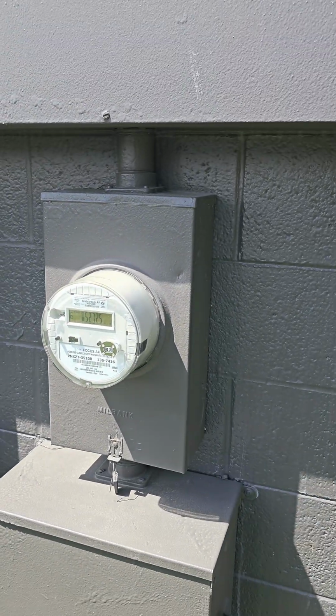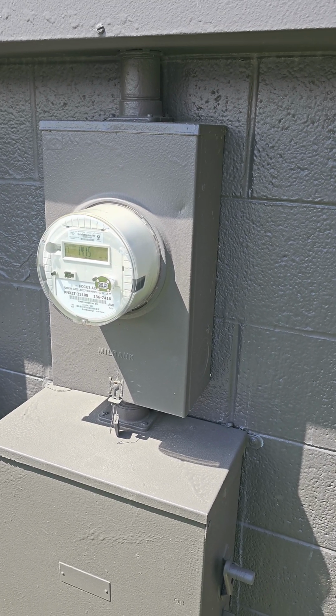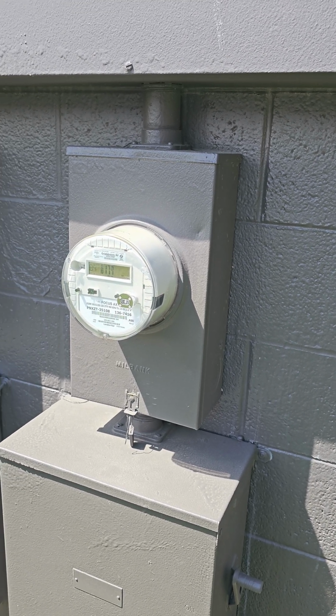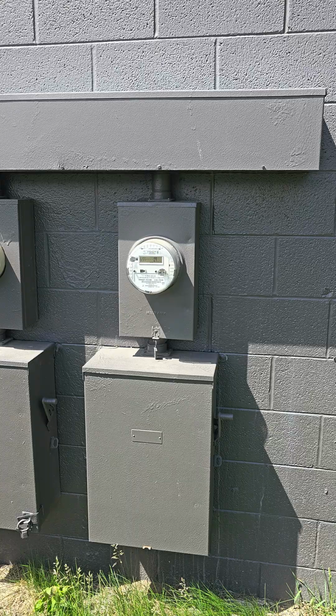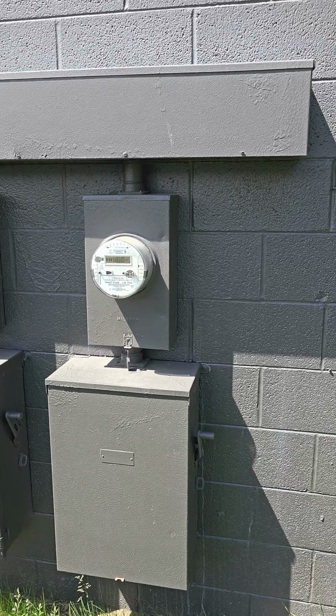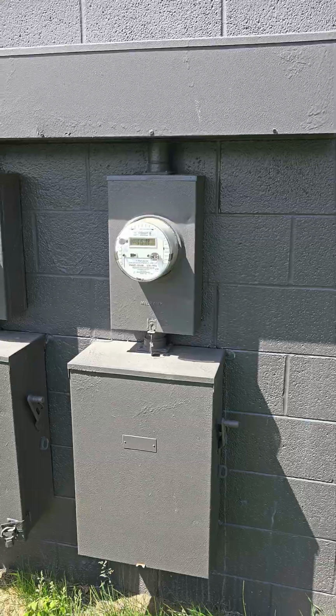Well, We Energies couldn't care less when they put this new meter in to treat the lugs with any respect. So, yeah. The socket is now messed up, and that's why we're losing B phase. I'm not going to blame We Energies, but let's be honest, it was working. They changed the meter and now it's not working, but of course, it's your equipment, so they don't care. And a couple thousand dollars later, because we got to change a meter socket.